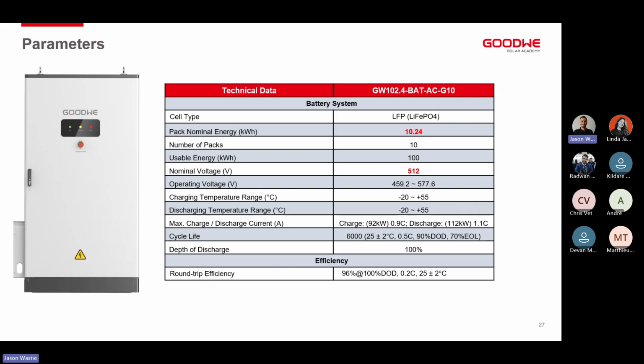Again, we have this conversation relatively often. Should we be discharging our batteries down to 100%? In my opinion, no. I don't think it is very good for a battery to run down to complete 0% all the time. We want to keep some form of a buffer on the bottom end of the cells, just so that if the power is out for an extended period of time and we can't recharge the batteries, at least there is a little bit more power available for us to keep the battery alive and keep everything working as it is intended to. Between 85 and 90% usage of the battery is where I feel it would be a lot better, and obviously be able to use the battery fully.